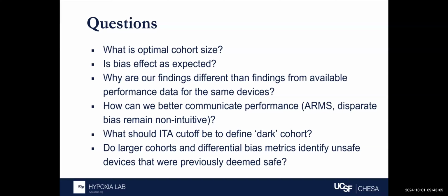I did note the discrepancy between finding seemingly very large differences across race and skin tone in the individual levels in your individual device testing, with nonetheless the fact that essentially all of those would have passed the proposed FDA standards, which seems to me to be a substantial concern that the FDA standards were built on technical feasibility rather than safety, and raises the concern that they may still let through potentially unacceptable levels of racial differentials.